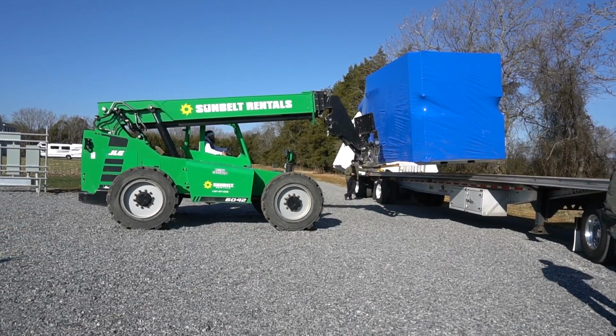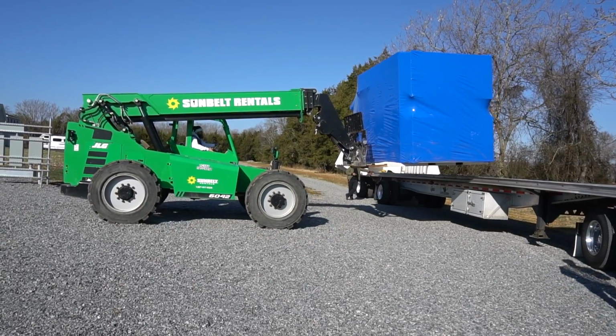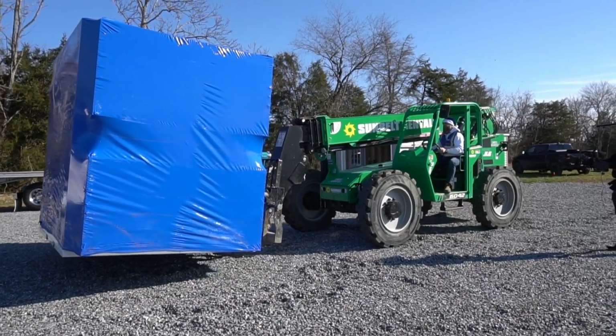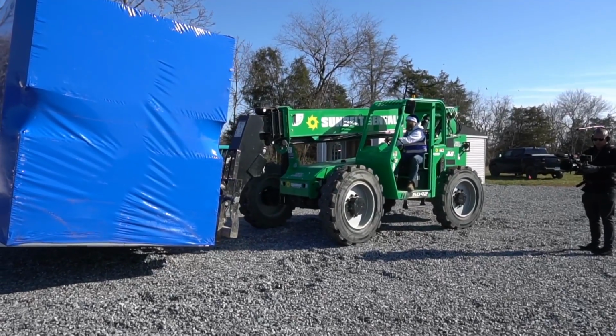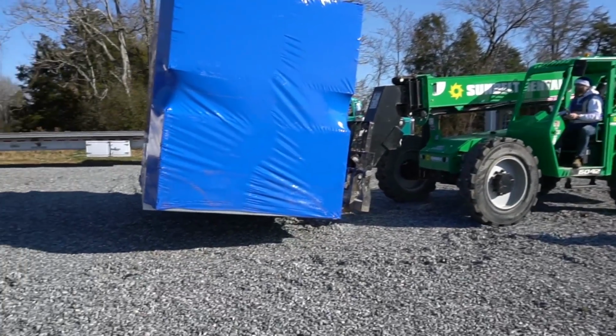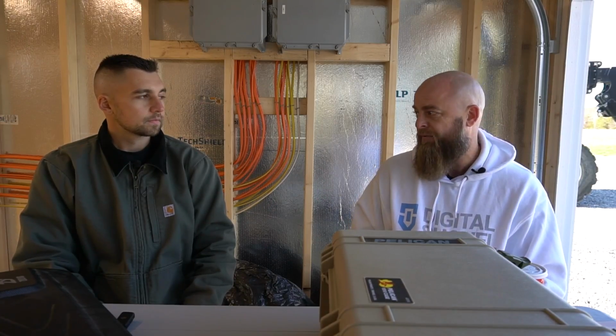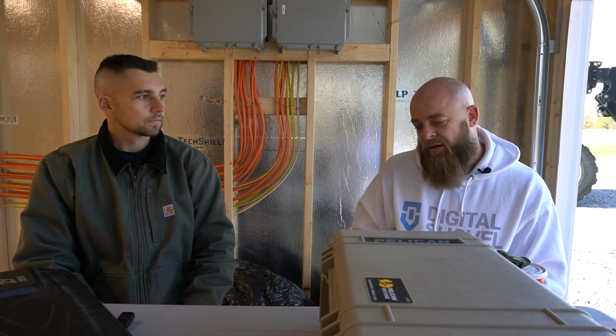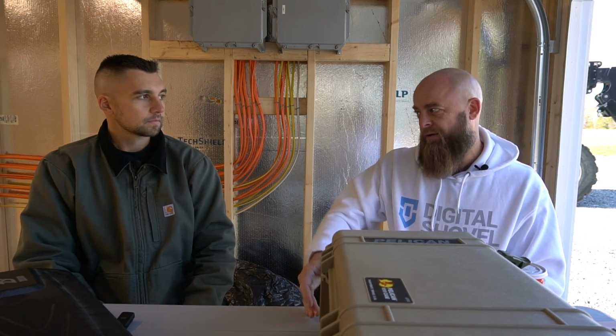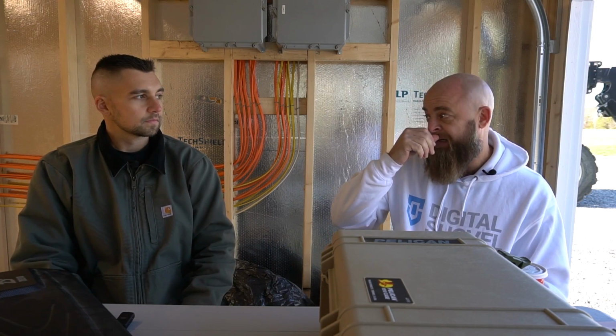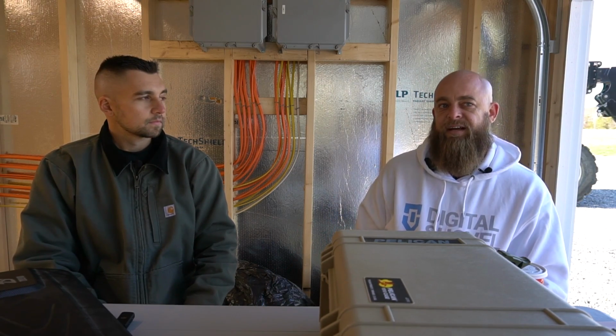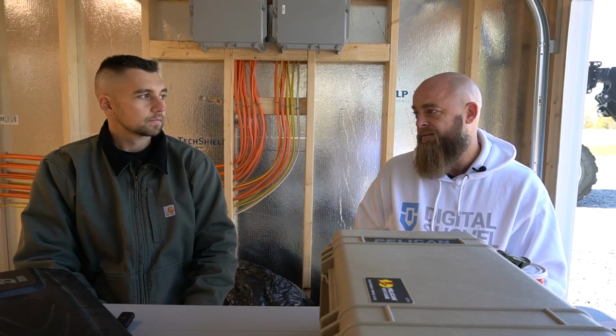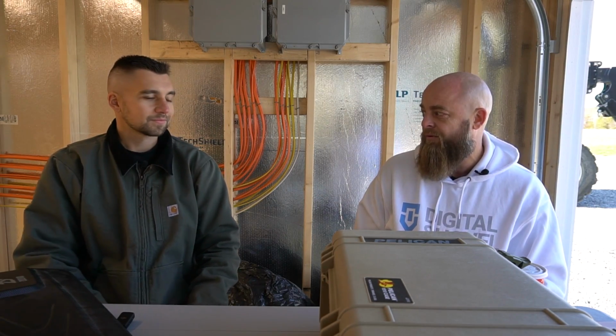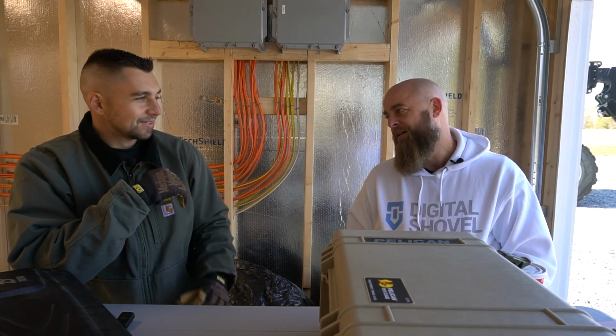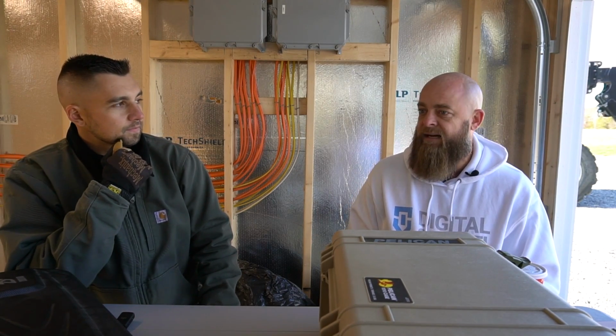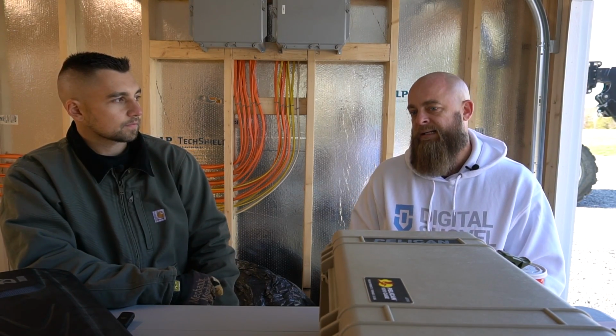With this setup, we can just grab it with a forklift, take it off, put it down a lot easier. That helps significantly because although this is a rural area, some of our client sites are a 4 or 5 hour drive from civilization, so you're paying for a crane for like 3 days - day in, day working there, day out. That's 15-20 grand on a 40-foot container with a 110-150 ton crane. In some of these rural locations it's closer to 20-25 grand. With this, you can rent a forklift, drop it, take it off a lot easier, so that helped with a lot of those problems.